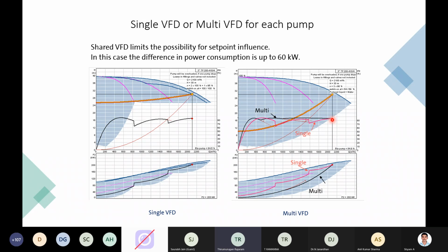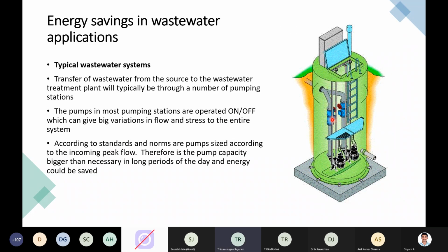So when you design a system for any water distribution application within thermal power plants, adapting a multi VFD system makes a lot of impact on your energy consumption. The impact is not only seen on surface mounted pumps. It is also visibly seen on your submersible dewatering pumps, because in any power plant you can find at least hundreds of submersible dewatering pumps here and there, to dewater liquids, for flood dewatering, or pond dewatering, or to pump out sewage from one place to another.